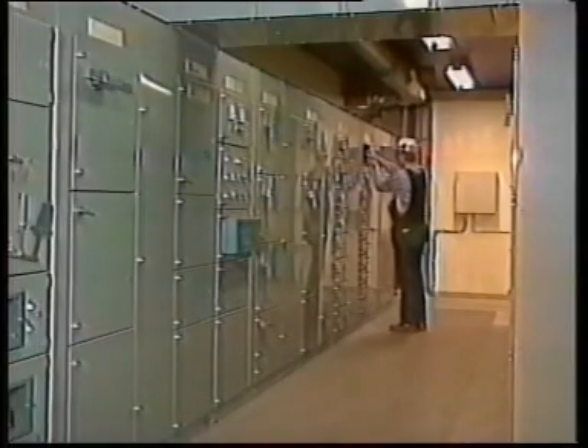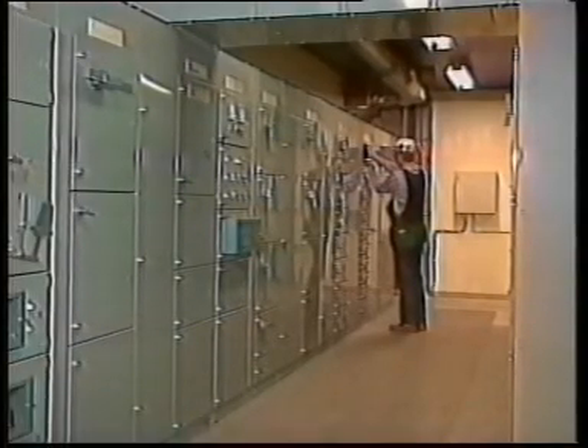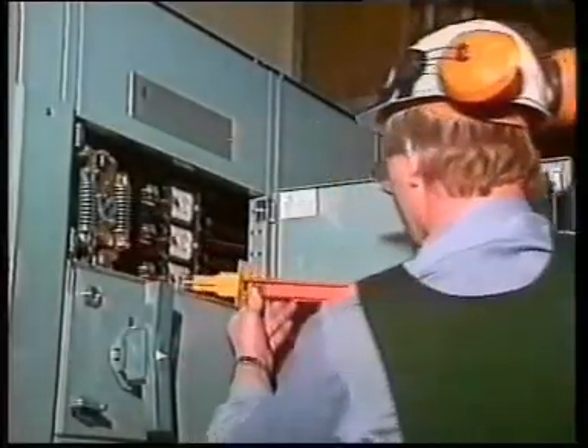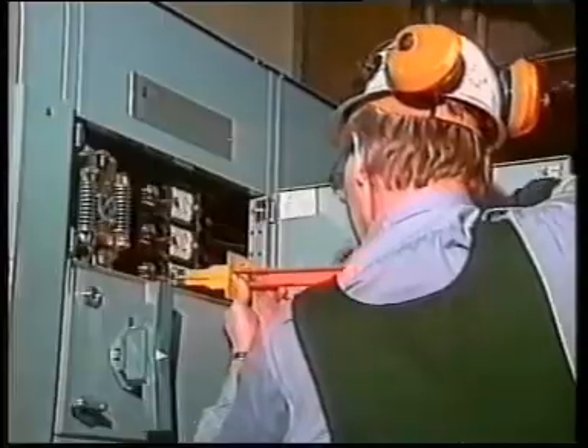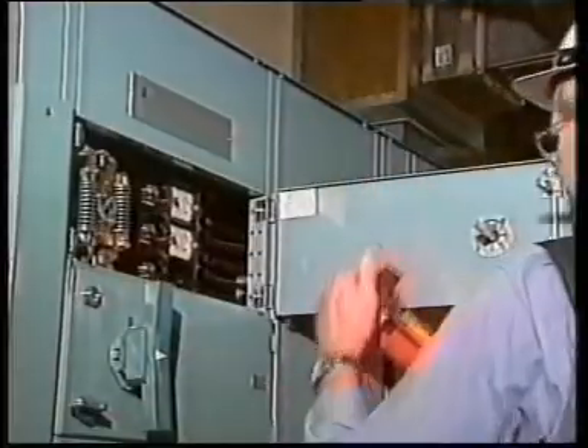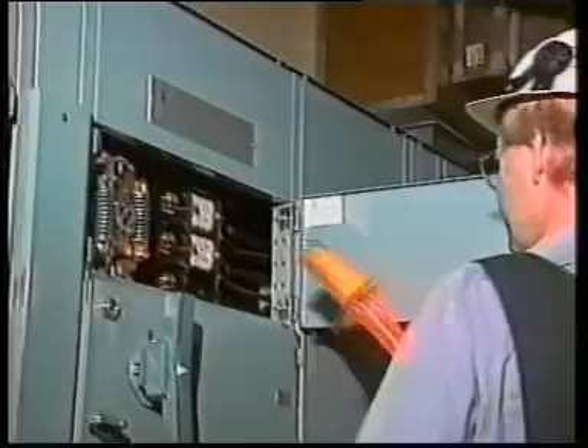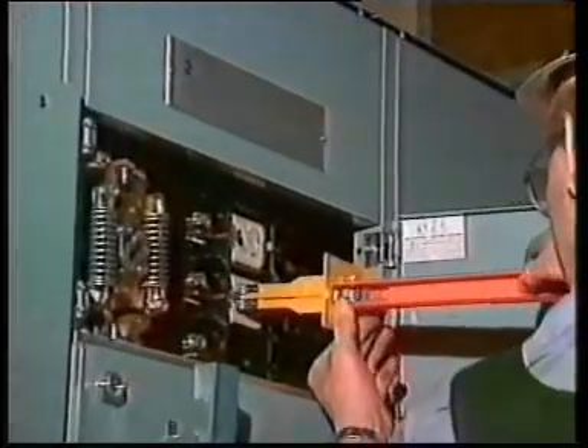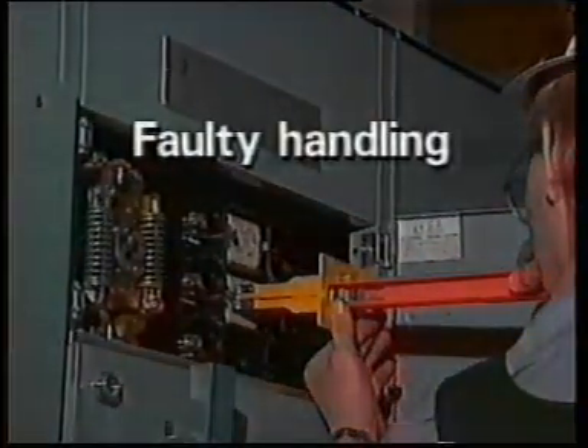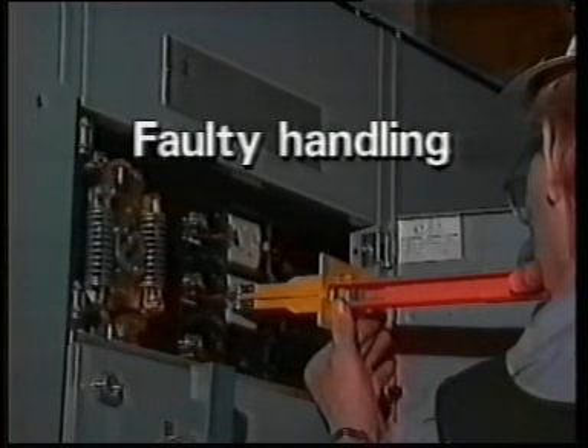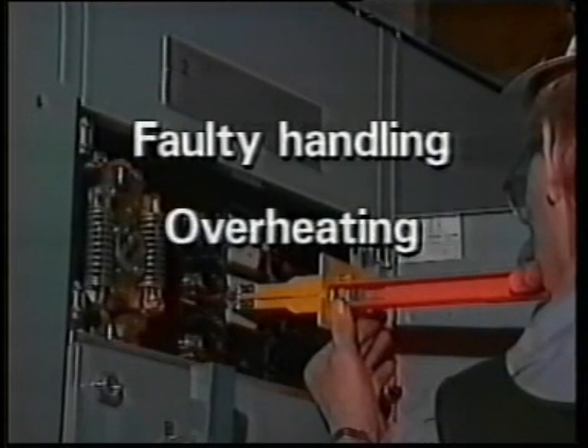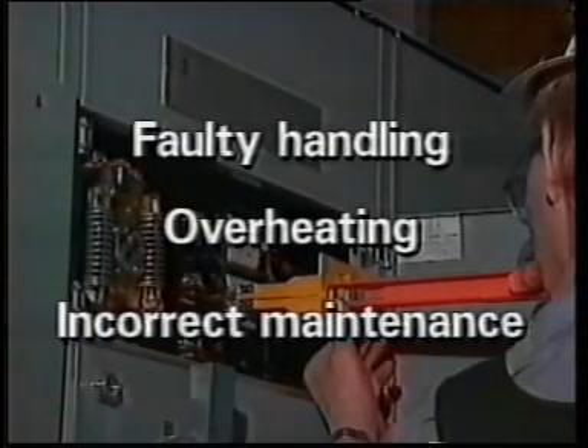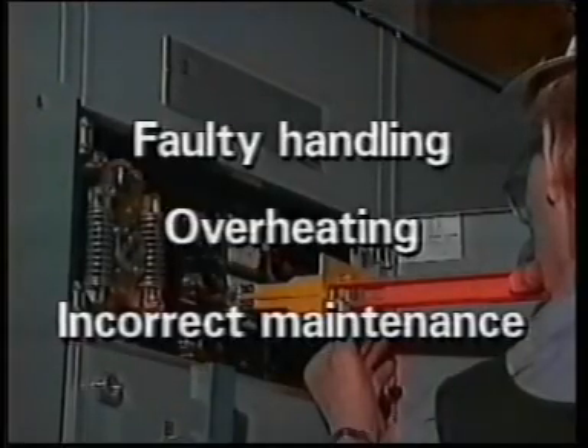copperwork. In recent years, major resources have been devoted to enhancing safety and reliability in low and high voltage switchgear. But despite the fact that modern switchgear is much safer than previous designs, the risk of an arc occurring can never be entirely eliminated. The most usual causes are faulty handling by erection and maintenance staff, the human factor, overheating, weakening dielectric strength and insulation, and mechanical defects due to insufficient or incorrect maintenance.